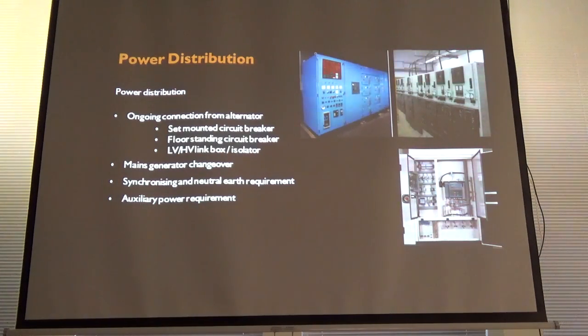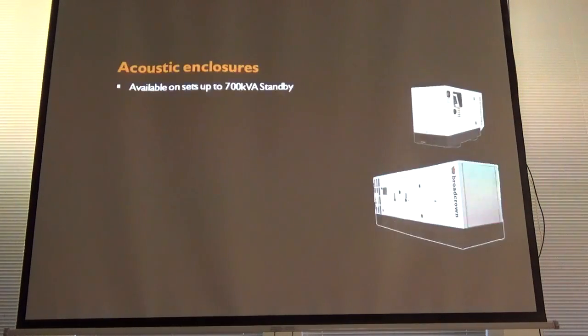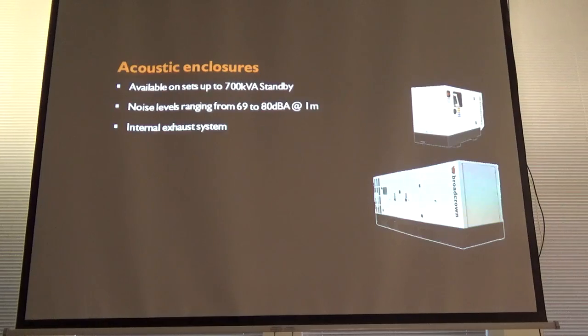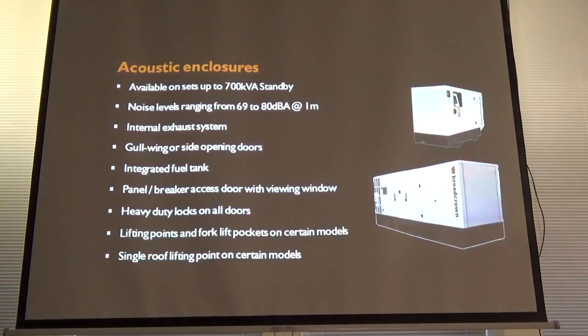We're looking at that. We do have some units actually at the moment. Say on a construction site, a construction company will say, I want a standard 20-foot power box unit, which is 1 megawatt, 1250 kVA, prime rated. It's a very compact unit. You'll see one of the photographs in a few moments actually. They might, on site, run that unit. They might be consistently running it.